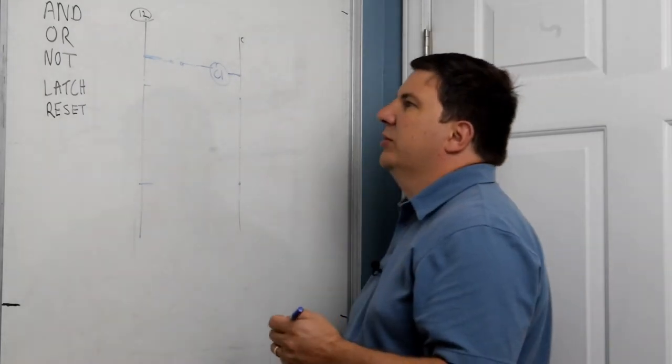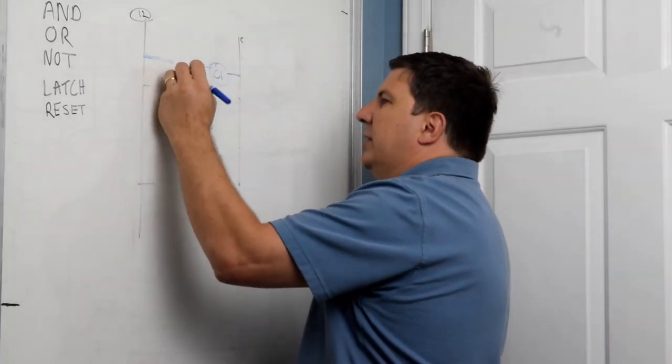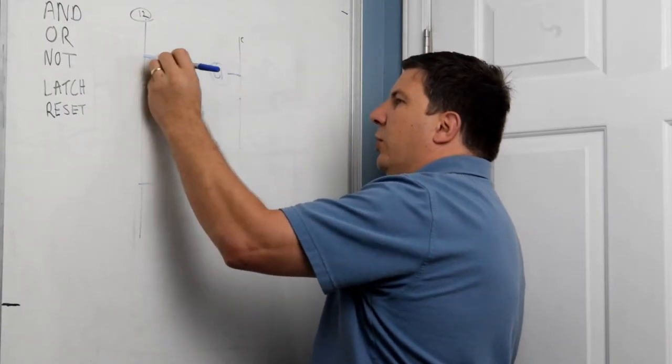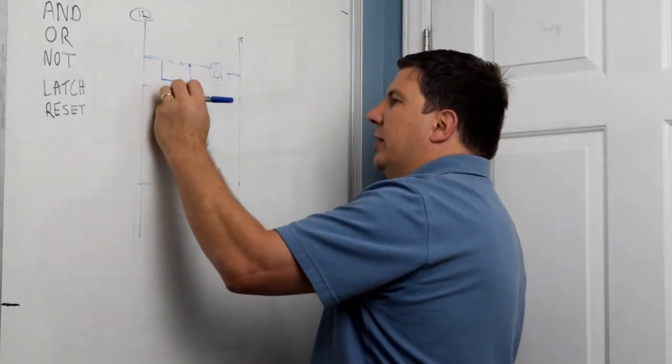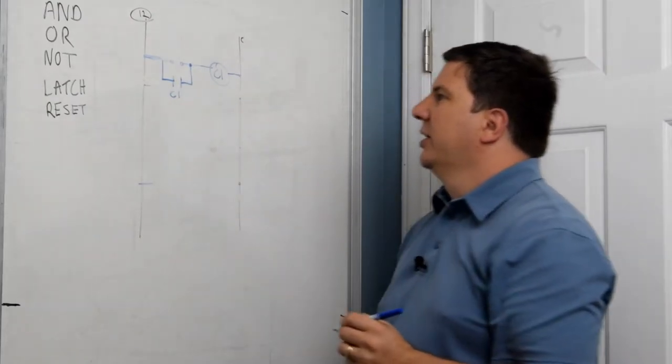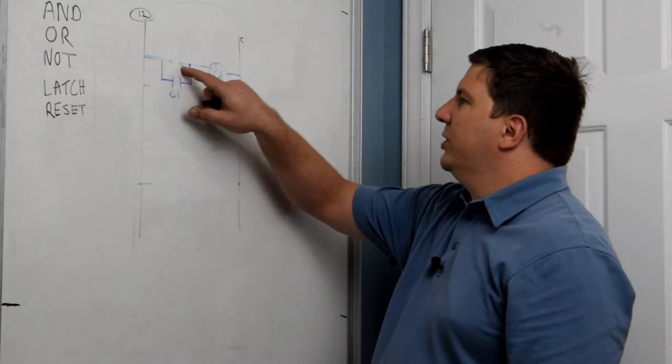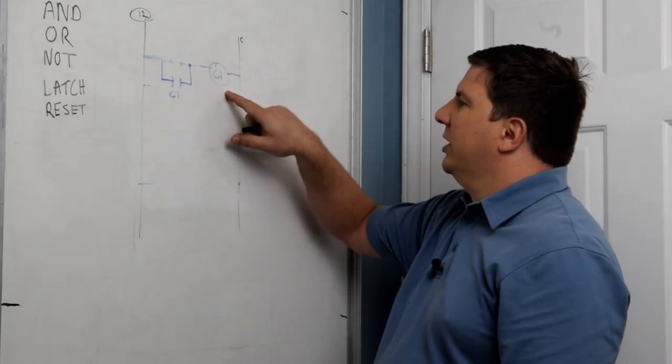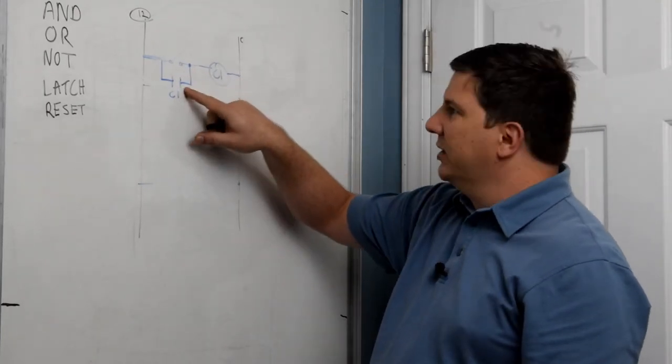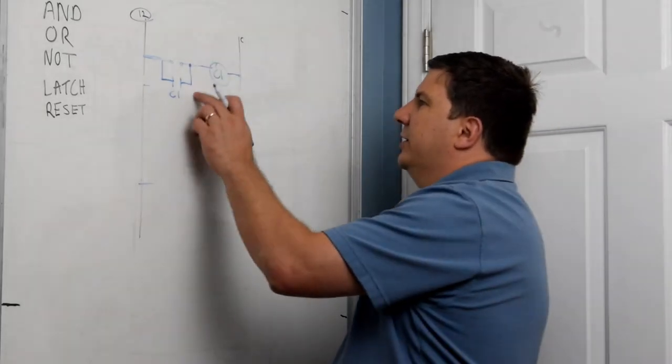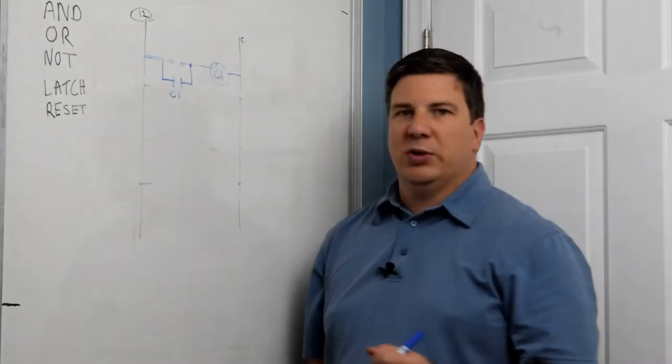So how we do this is we trick it essentially into thinking that somebody's pushing that by taking the first coil of that motor and using that coil to hold the motor back on. So now we have, I switched it on, C1 comes on and this coil energizes. So now I can de-energize this and take my finger off the button and it'll still make a path to keep C1 on.